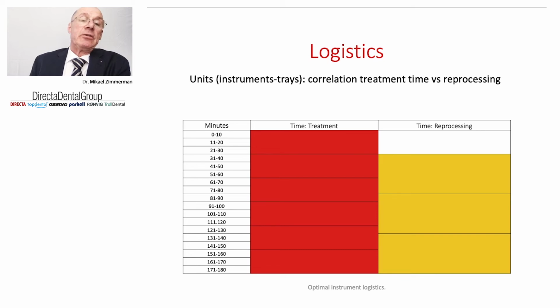Another way to calculate the number of instruments needed: if you see the red boxes, that is the treatment time when the instruments are actually in use at the operatory when treating the patient. If the patient treatment is 30 minutes, and we calculate that those instruments need 50 minutes to be reprocessed, then we can have 1, 2, 3, 4, 5, 6 red boxes, 6 treatments, each one 30 minutes. With those 6 treatments of 30 minutes, if the reprocessing time of the instruments is equal to 50 minutes, we will get in level with each other at the point of 180 minutes, in 3 hours.